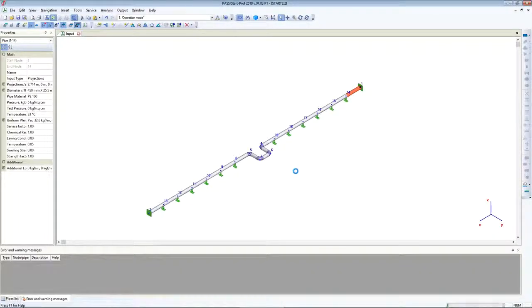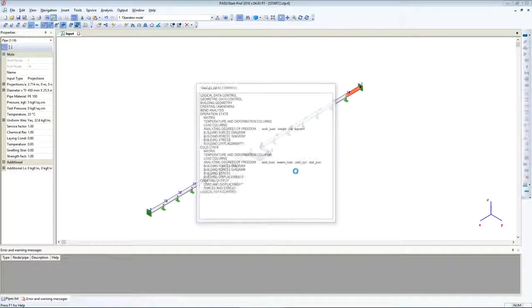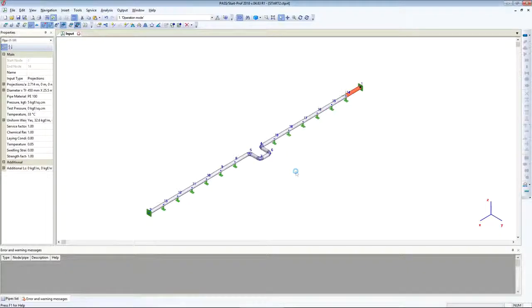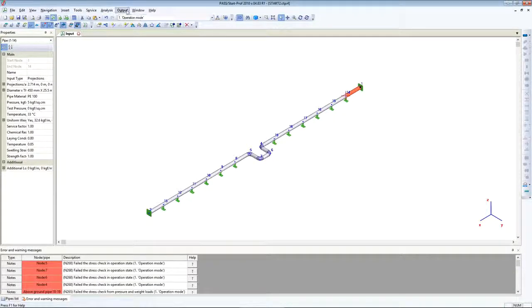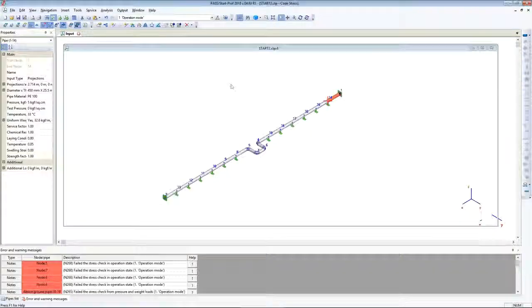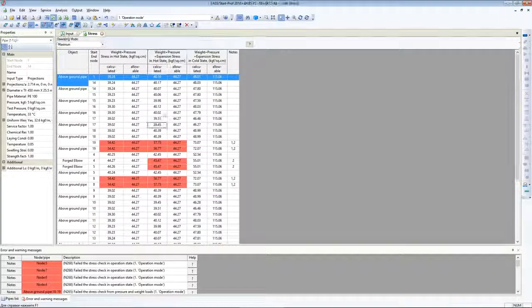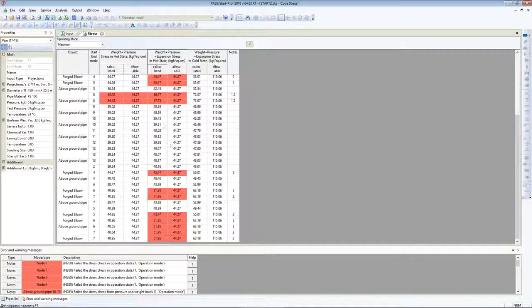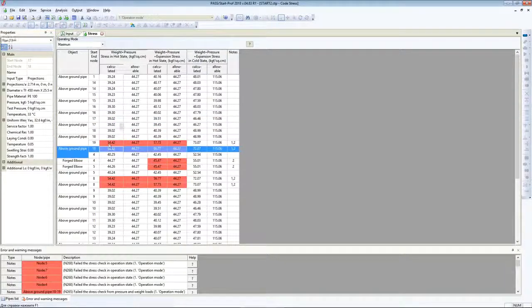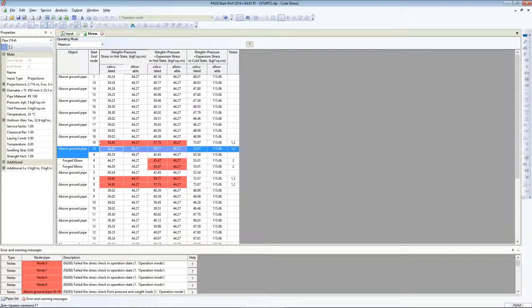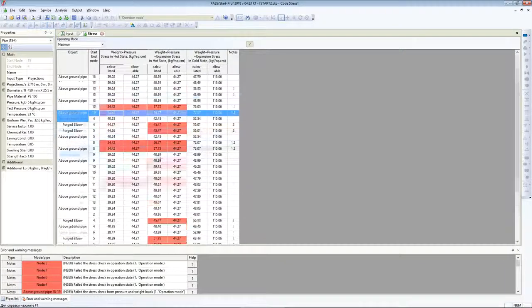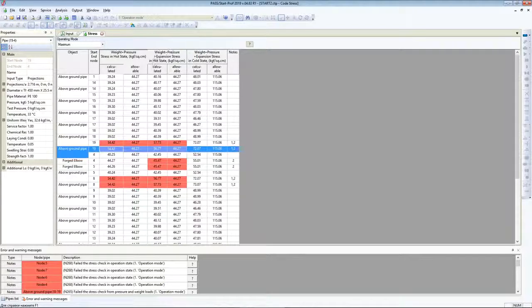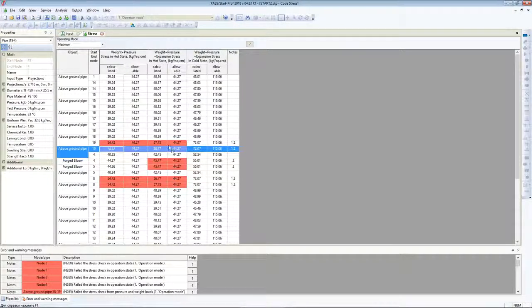Let's run analysis. Analysis is done. Let's check results. It's pipe stress - it didn't pass. Here it didn't pass the weight loads, and here it didn't pass the weight and expansion loads.